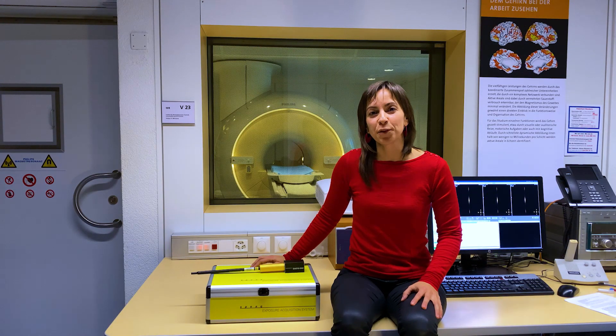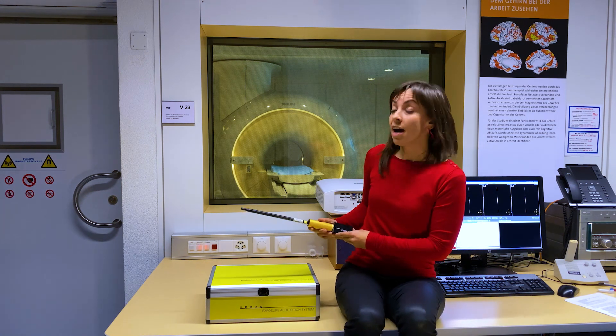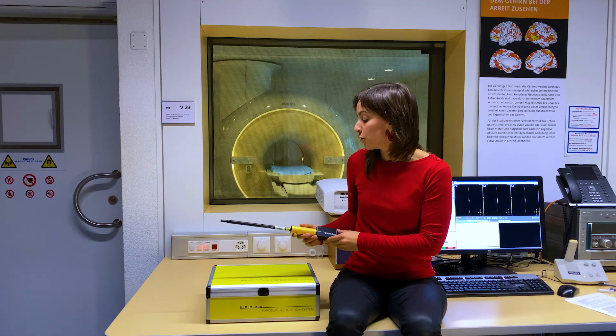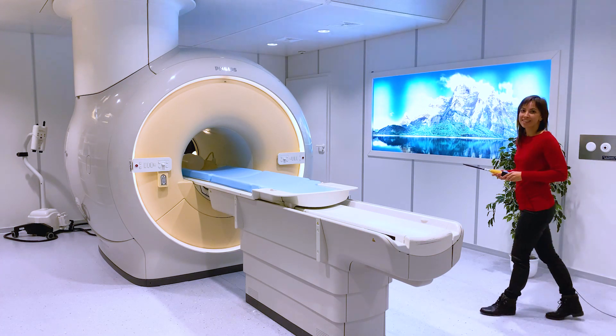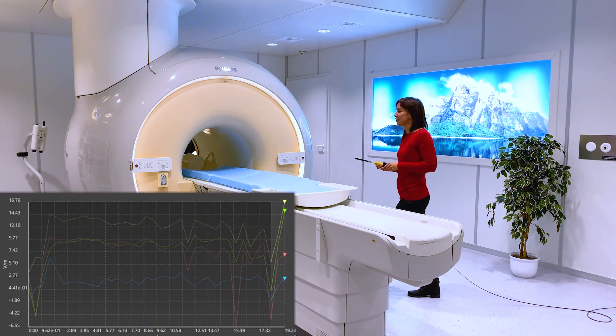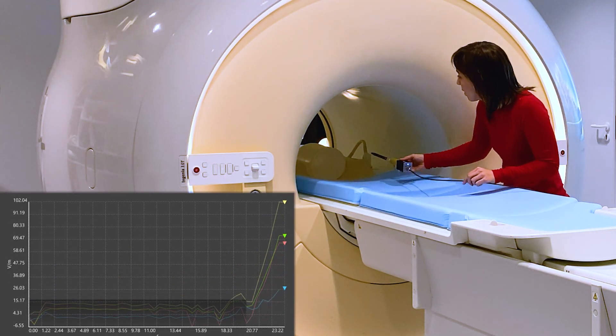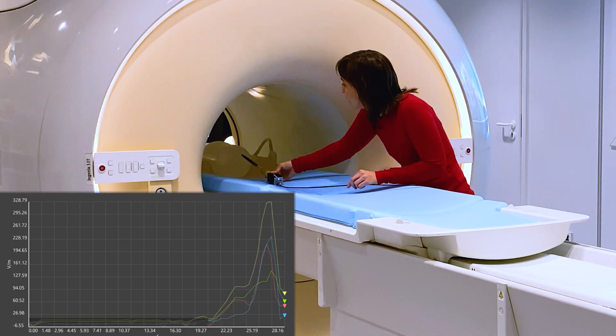We are here at the Institute for Biomedical Engineering at ETH Zurich and the University of Zurich, and we are going to do a measurement in a hostile environment. We have here behind us a 3T scanner and we are going to walk inside with the EC6 and our probe and measure the field when we walk towards the scanner. As I walk towards the scanner, you should see the field increasing. You will also see that the fields are much higher when we are at the end reach than when we are at the isocenter.